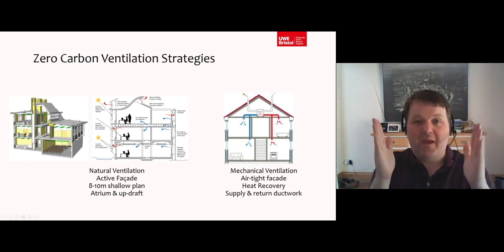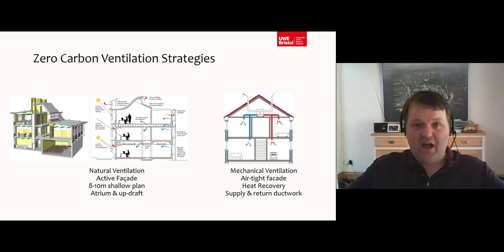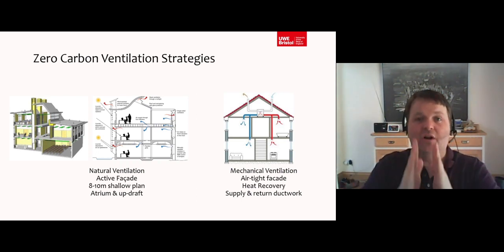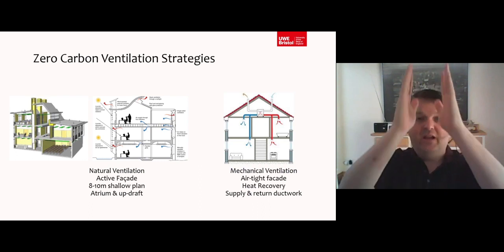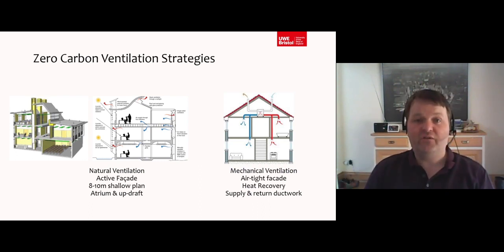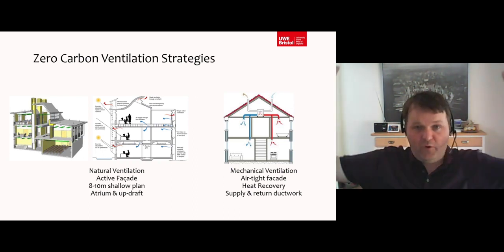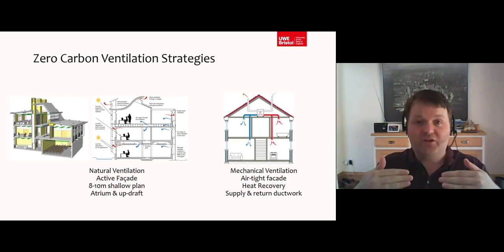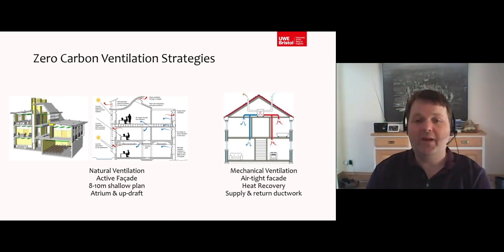If you're an architect, the main shape is from your facade about 8 meters in, and then the air wants to turn and go up. So that basic shape is the determining factor of your naturally ventilated building. Quite a few times I get architects coming to me, student architects, and they have a fully designed building. They go, now I want to make it naturally ventilated. And I'm going, I'm sorry, you have to decide that at the beginning because it has such a big instrumental influence on the shape of your building. From your facade, about 8 meters of horizontal movement before that air wants to turn and go up. That's about the main shape.